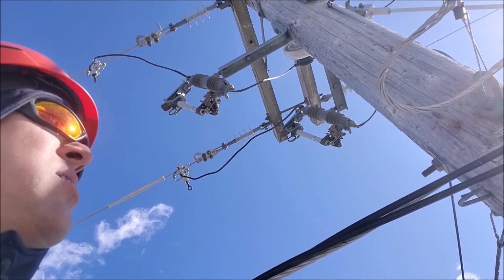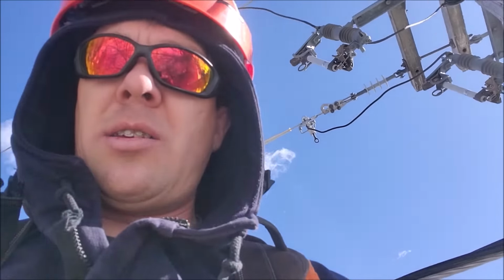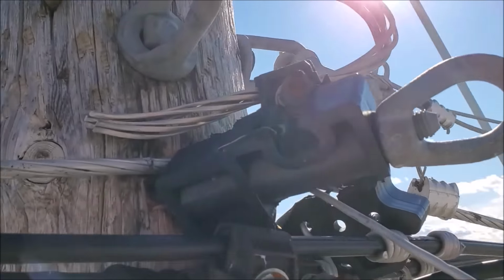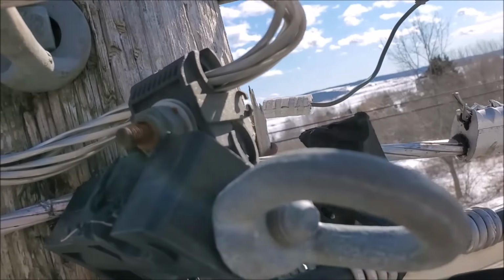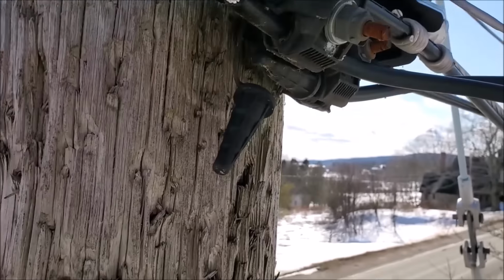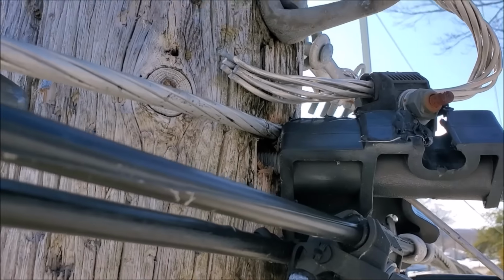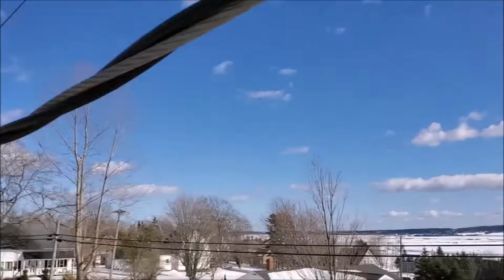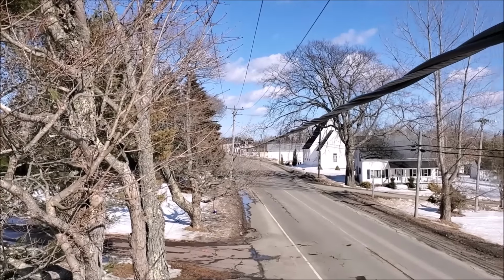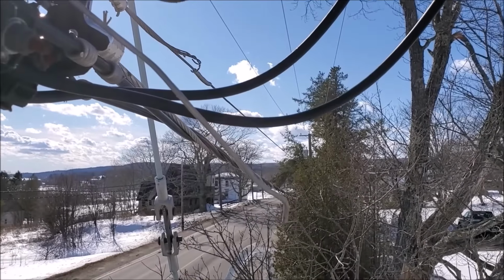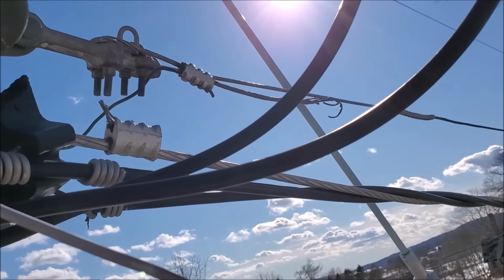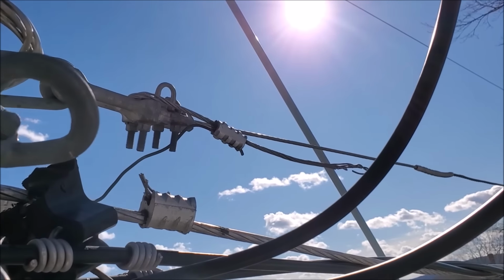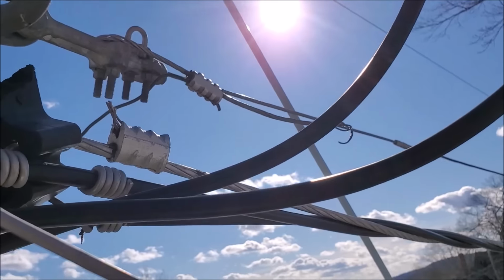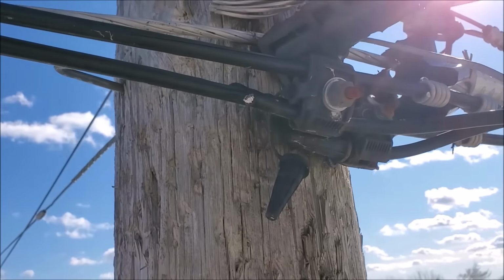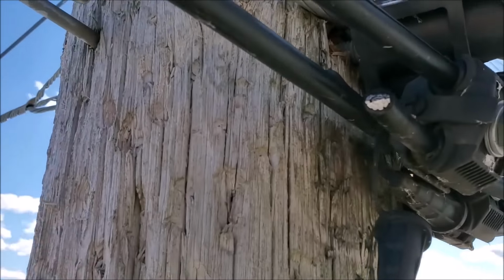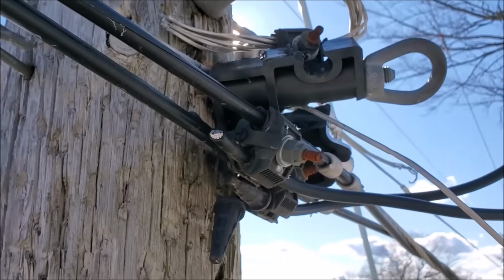Yes, sir. All right, take a look at this. The neutral connection actually got broken right off the pole. Now, it's hard to say what happened here. There could have been a vehicle accident that bumped the pole and shook things up. Could have been a tree come down. I see here that the neutral was actually busted off on the secondary side as well as the stirrup there. We've got a bare spot right here. Let's get this fixed up.